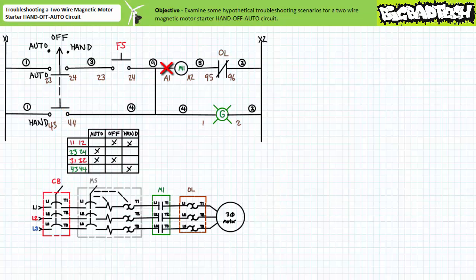Finally, if the wire four open occurs at the A1 terminal of the coil, neither the logic in rung 1 or rung 2 will start the motor. A mission critical operation might disastrously fail given neither the automatic or hand bypass can effectively energize the M1 contactor coil.